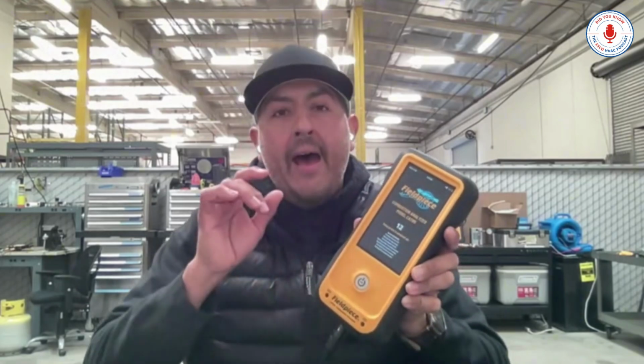Now, where you allow this warm-up is extremely important, because you want to let your combustion analyzer warm up in an environment where you have no carbon monoxide present and you are in fresh air. Okay. Now, pro tip: do not perform this process standing right next to your exhaust pipe minutes after you have just parked your service vehicle, as you might get traces of carbon monoxide during the warm-up process. But during this warm-up process, it is calibrating the oxygen sensor to ambient levels of oxygen, but it's also zeroing out the carbon monoxide sensor. So step one is proper warm-up of your combustion analyzer.